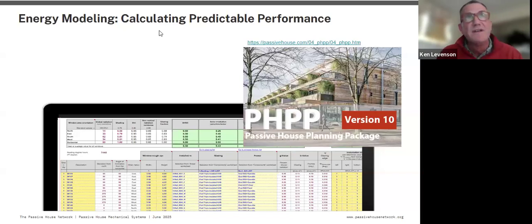This speaks to the mechanicals, since we want to be sure we can reduce those systems confidently. For example, that townhouse I did in Brooklyn — other similar townhouses installed 12 to 15 tons of air conditioning, just a standard rule of thumb for that building type. We did the calculations with Passive House and the PHPP, and came up with 3 tons of air conditioning for heating and cooling with a heat pump system. That's dramatic — and when someone is spending a lot of money on a home renovation and you're reducing the mechanical systems that much, you better be sure it's predictable.